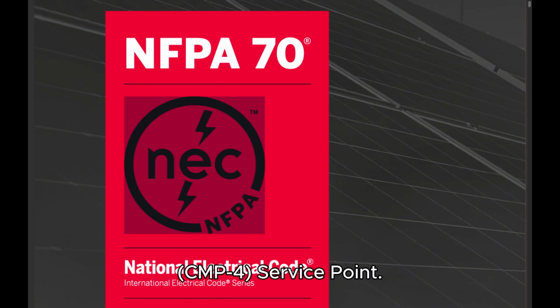CMP4 service point. The point of connection between the facilities of the serving utility and the premises wiring. CMP-4 informational note. The service point can be described as the point of demarcation between where the serving utility ends and the premises wiring begins. The serving utility generally specifies the location of the service point based on the conditions of service.